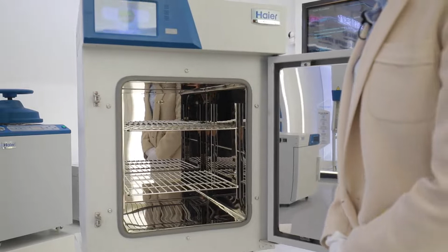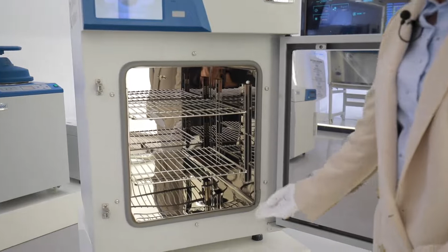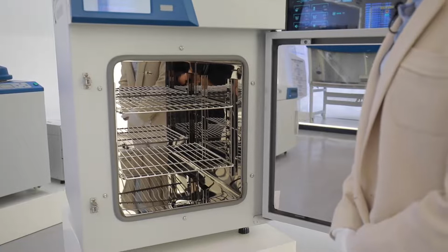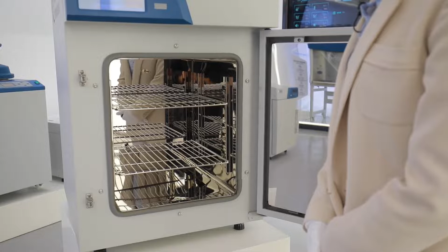And for our cabinet, we have 2 lock points. Compared with the single one in the middle, our design can give the cabinet a better seal. Inside the chamber, all the corners are round, which makes the cleanness of the chamber much easier. In our standard configuration, we only have 2 layers of shelves. As an option, however, for this model, customers can choose maximum 9 layers, and for the HFS160, customers can choose maximum 15 layers. Different from the direct heating method, our cabinet adopts the preheating air jacket type.